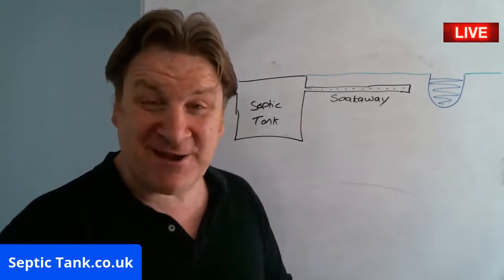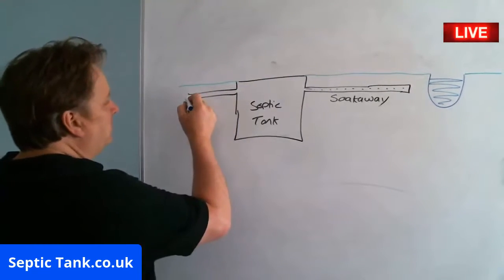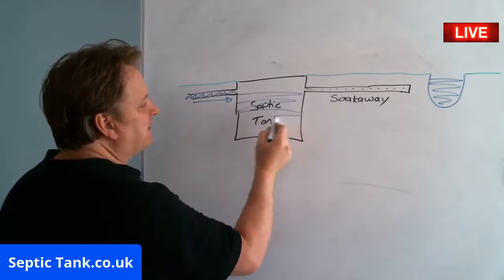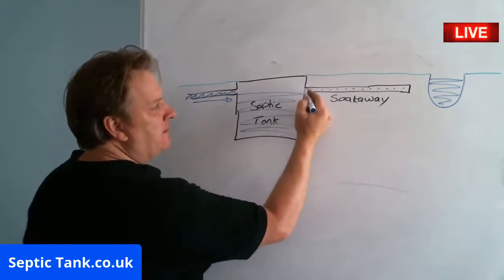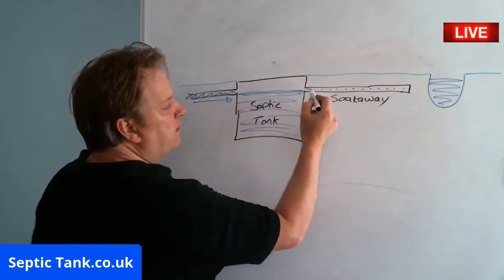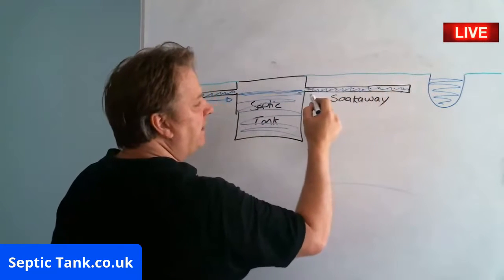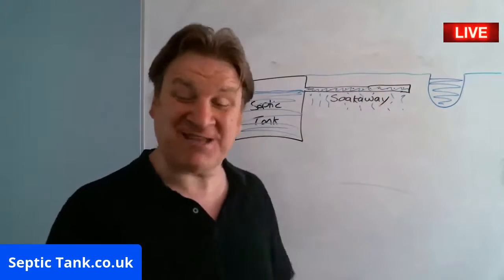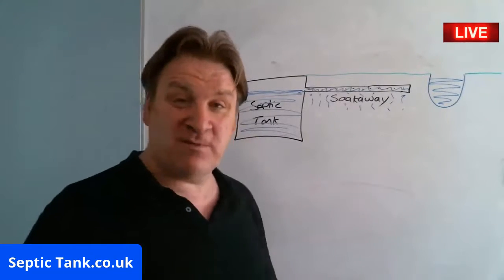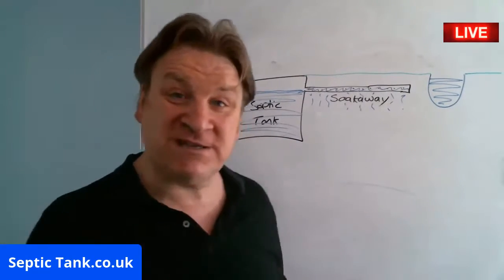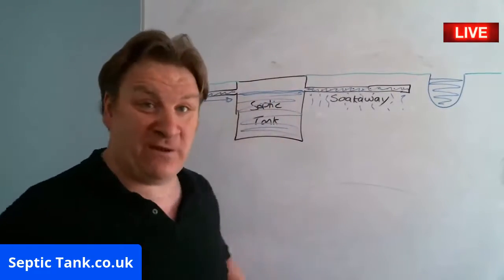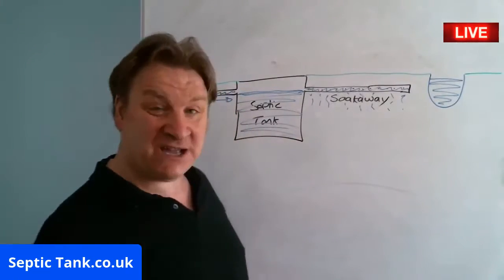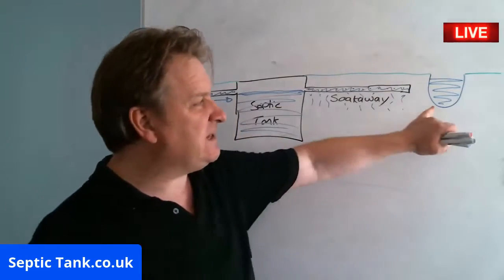Let me quickly explain how a septic tank works. Raw sewage in the form of wastewater goes into the septic tank, fills it up, and when it reaches a certain level, the wastewater then goes into the soak away and drains into the soil. The soak away is probably the most important component — if the water didn't soak away, the tank would overflow, stink, and back up to the house.